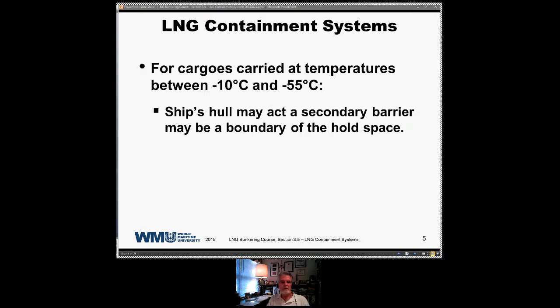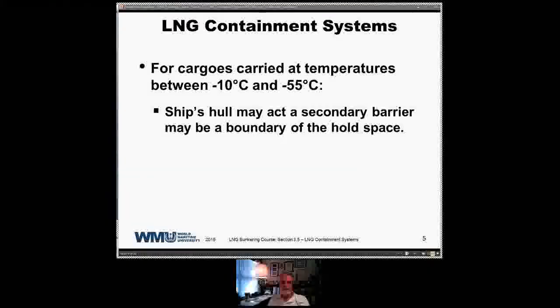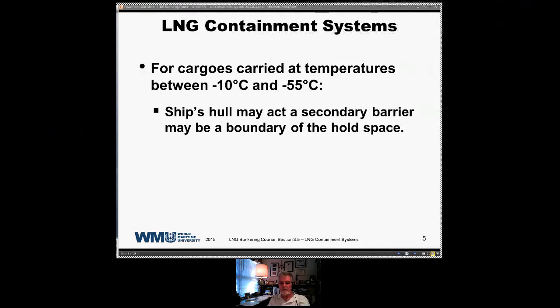That is going to be a demonstration of the behavior of materials when subjected to cryogenic temperatures. The first part of that segment is what happens to mild steel, ordinary carbon steel, when it's subjected to cryogenic temperatures and then struck with a force. And the second part shows what happens to a similar piece of material made out of stainless steel. This is the most common material used in cryogenic tanks, stainless steel or aluminum alloys, which react the same as stainless steel when subjected to cryogenic temperatures.